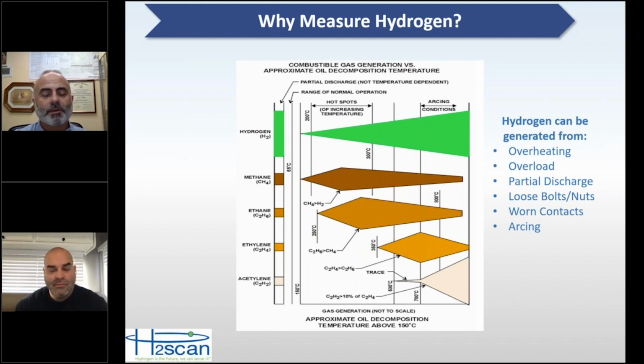So typically what you see with hydrogen is when the hydrogen is generated, hopefully it's just due to a temporary event, overloading or something overheating very quickly, and that will lead to some amount of hydrogen being produced and possibly other gases. And then once that hydrogen's produced, if whatever happened to cause that to be produced goes away, then over time, normally the hydrogen will escape out of the transformer. And usually, if it's not a very tight transformer, that hydrogen will be gone very quickly, within days.